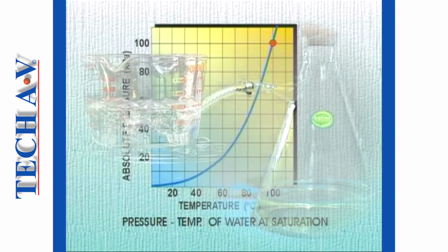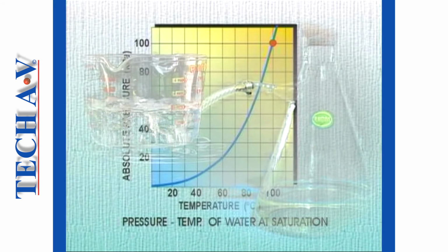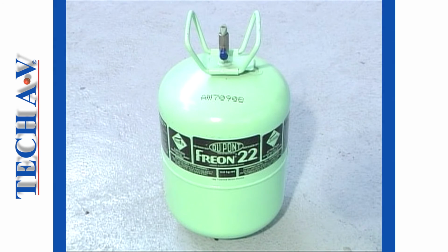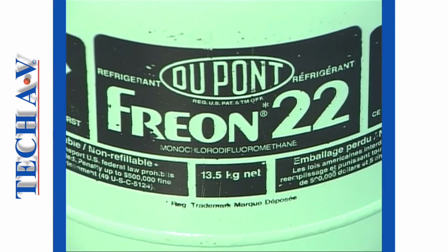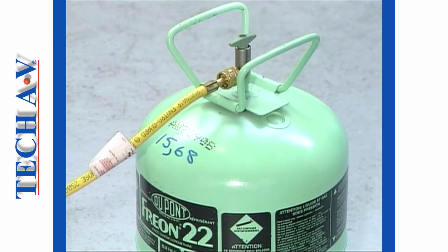Utilizing these scientific facts, we can create the conditions for true refrigeration. Liquids used in evaporative refrigeration systems have very low saturation points. A typical refrigerant, used commonly in many commercial systems, is a type called refrigerant 22, or simply R22. This refrigerant, at atmospheric pressure, will boil vigorously at a temperature around -40 degrees.